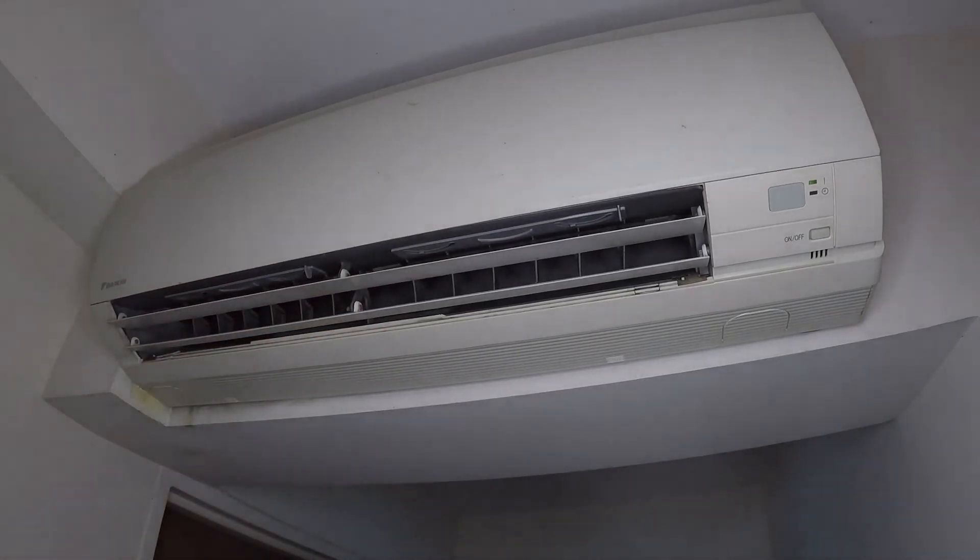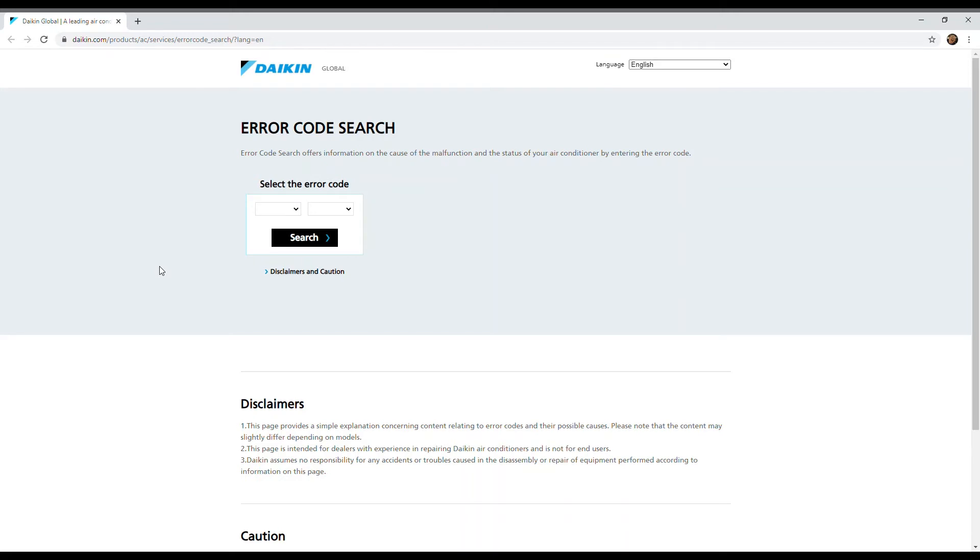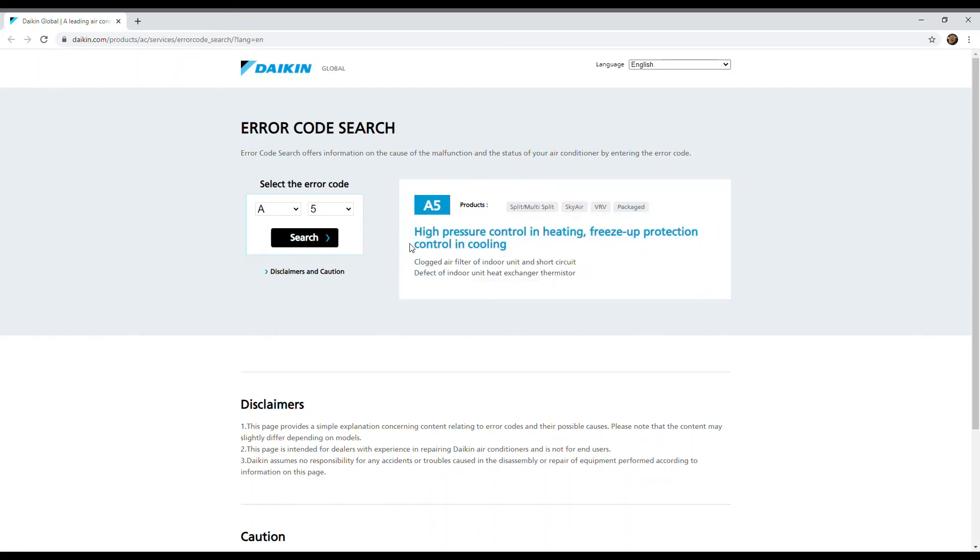So the error code for mine is A5. I'll look it up on the Daikin global website — not the local Singapore site, the global one. I'll put the link in the description so you can check it out. Searching A5, the result shows: high pressure control in heating, freeze-up protection in cooling.